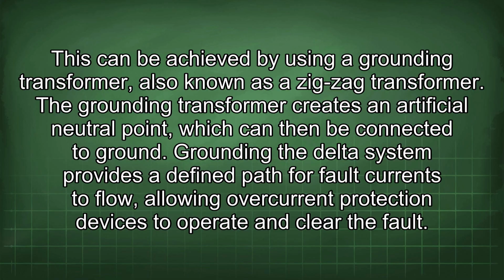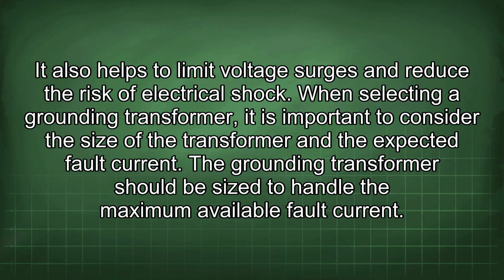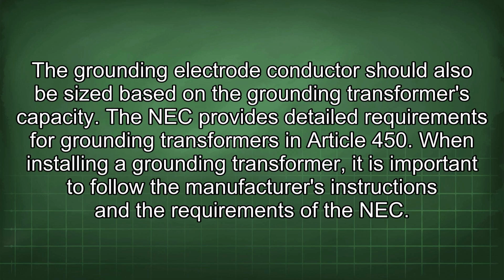Grounding the delta system provides a defined path for fault currents to flow, allowing overcurrent protection devices to operate and clear the fault. It also helps to limit voltage surges and reduce the risk of electrical shock. When selecting a grounding transformer, it is important to consider the size of the transformer and the expected fault current. The grounding transformer should be sized to handle the maximum available fault current. The grounding electrode conductor should also be sized based on the grounding transformer's capacity.